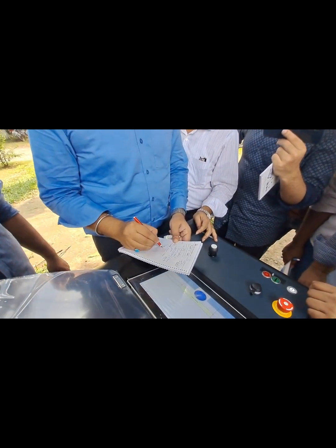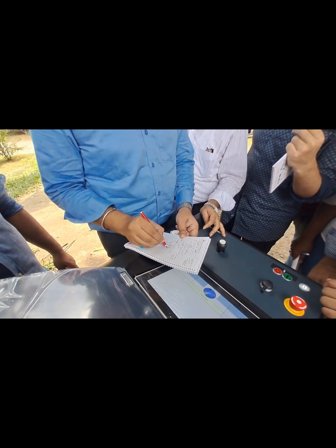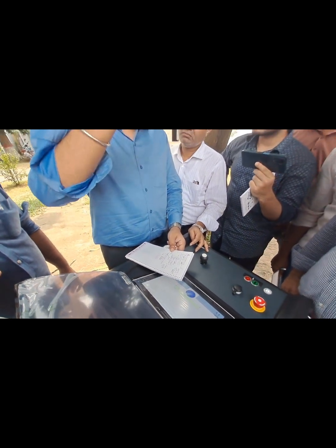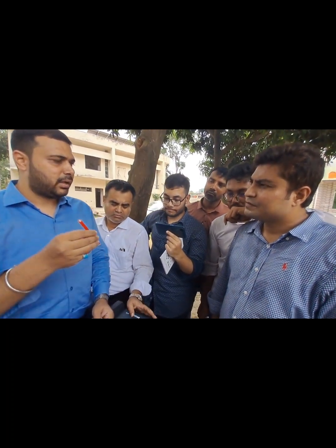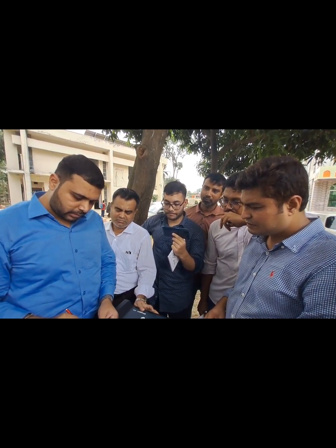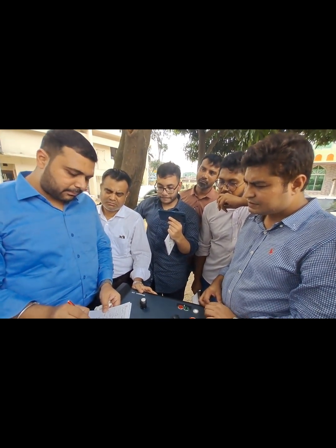If my resistance values are in kilo ohms, then I can consider it a pinhole fault. Like some nail is inserted in the conductor and it has not perfectly gone to the armor. Sometimes it conducts, sometimes not, which is why the resistance values are in kilo ohms. You know the situation now? If the values are in this range, I will apply the ARM method.